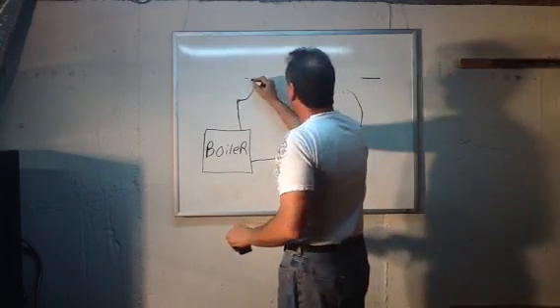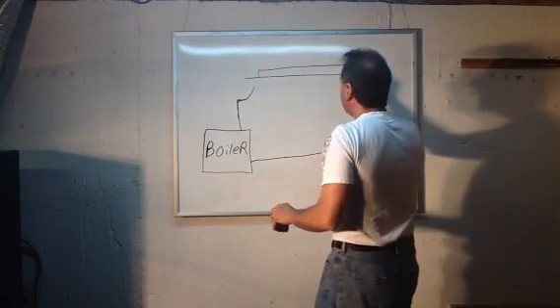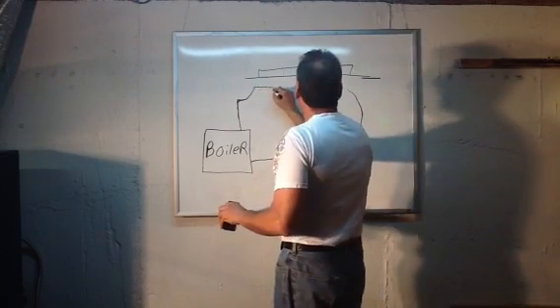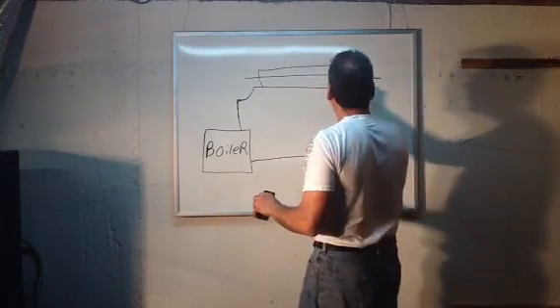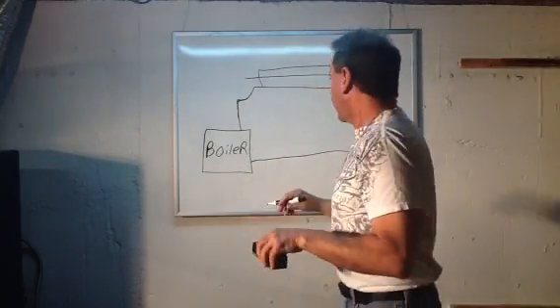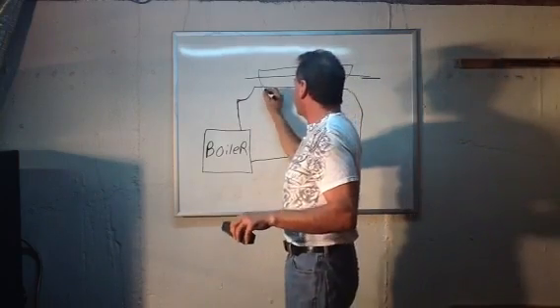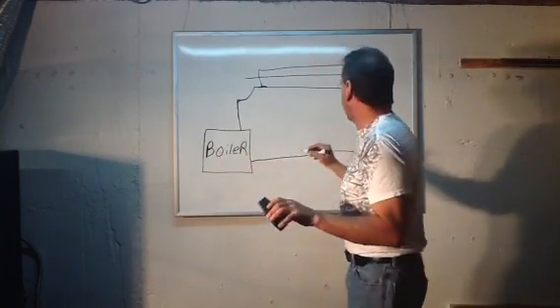You're never going to get that out of those monoflow tees. So if they did that and you have baseboard up there and it's not getting warm, it's because somebody simply went off the two half-inch monoflow tees. There's a simple way of checking it: you can go downstairs and look and see if there's tees there. There should never be tees at baseboard, it should always be elbows.